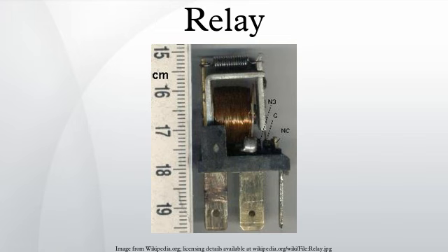Solid-state relay. A solid-state relay is a solid-state electronic component that provides a similar function to an electromechanical relay but does not have any moving components, increasing long-term reliability. Every solid-state device has a small voltage drop across it. This voltage drop limits the amount of current a given SSR can handle. The minimum voltage drop for such a relay is a function of the material used to make the device. Solid-state relays rated to handle as much as 1,200 amperes have become commercially available.